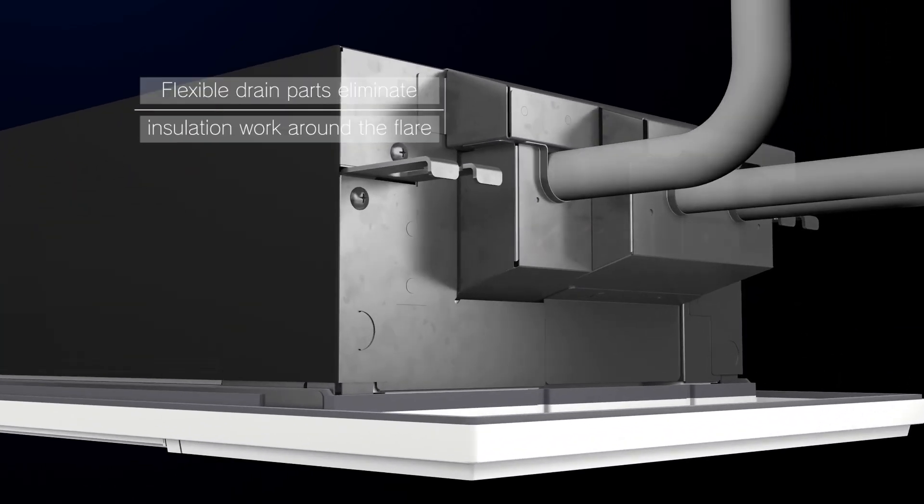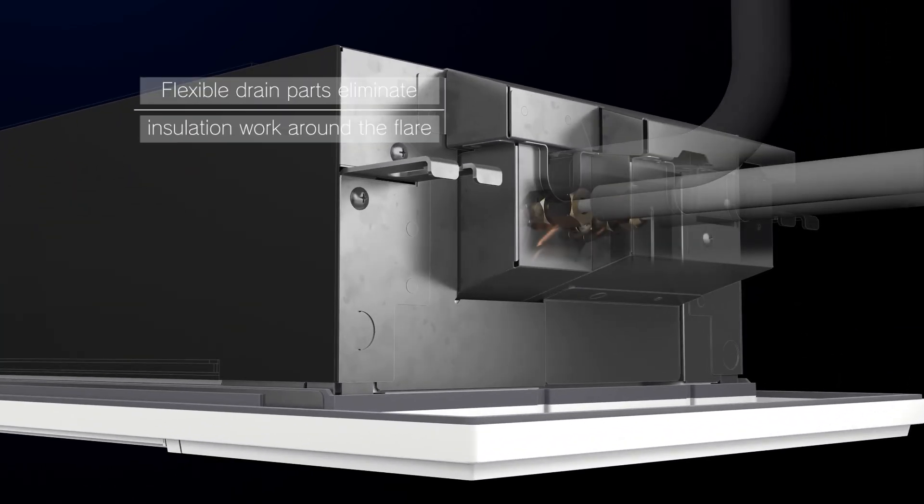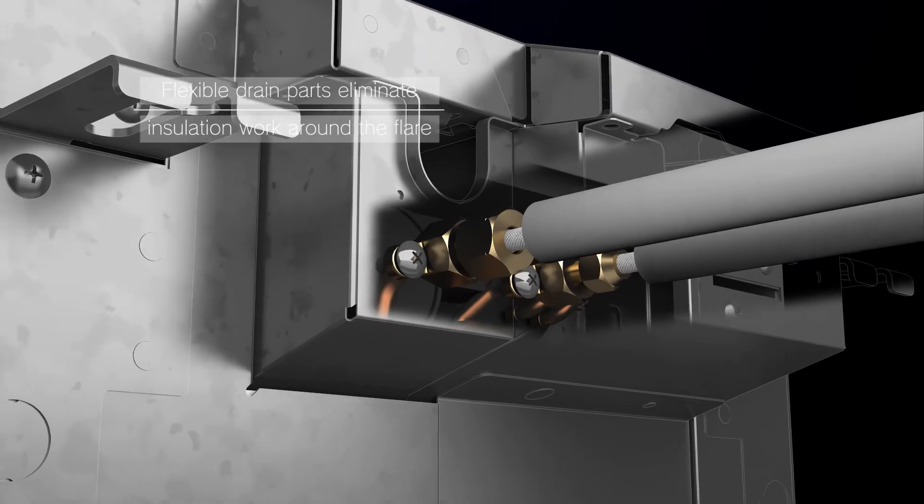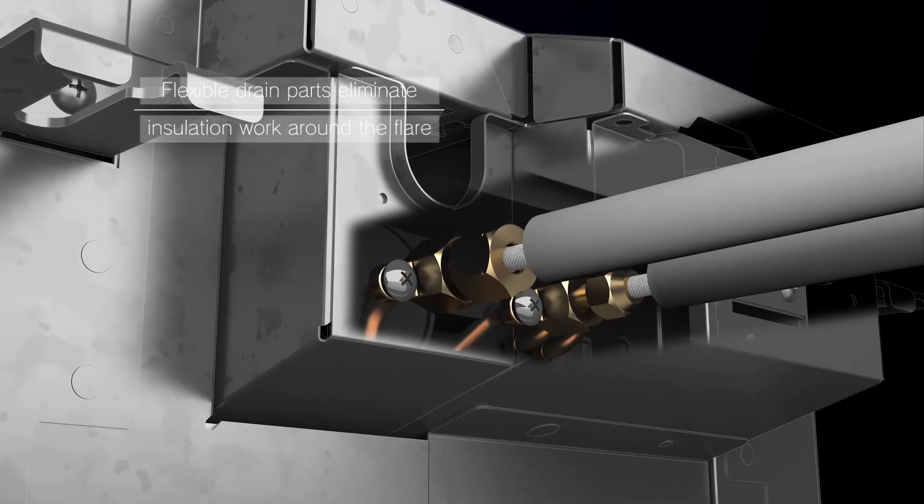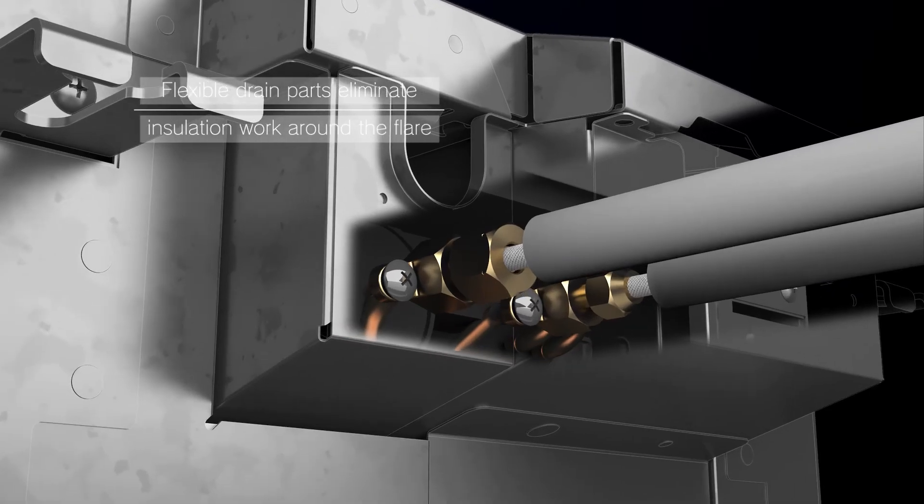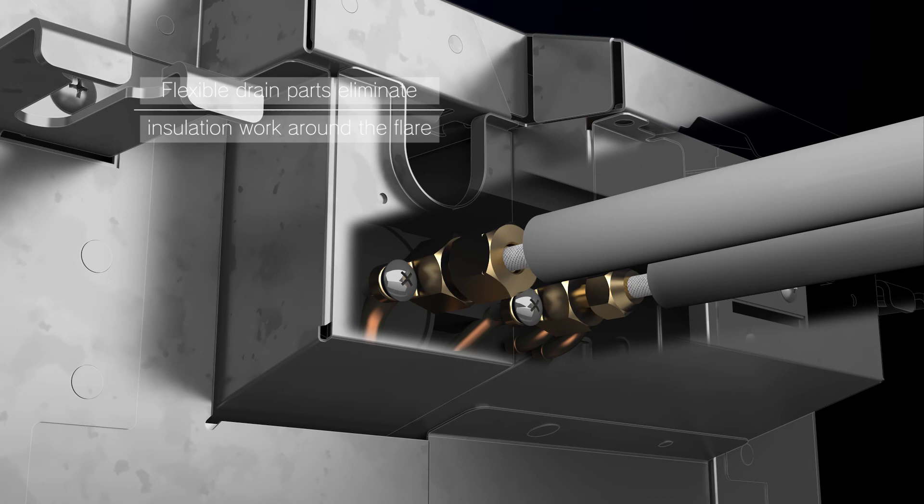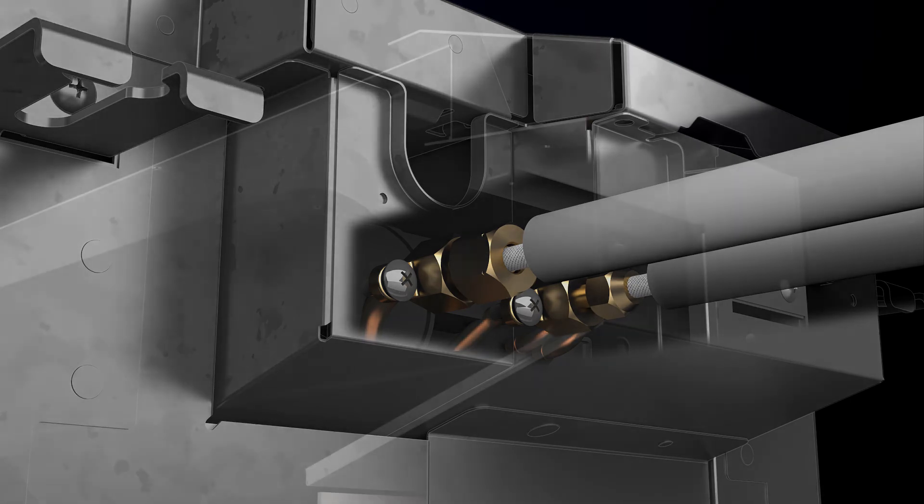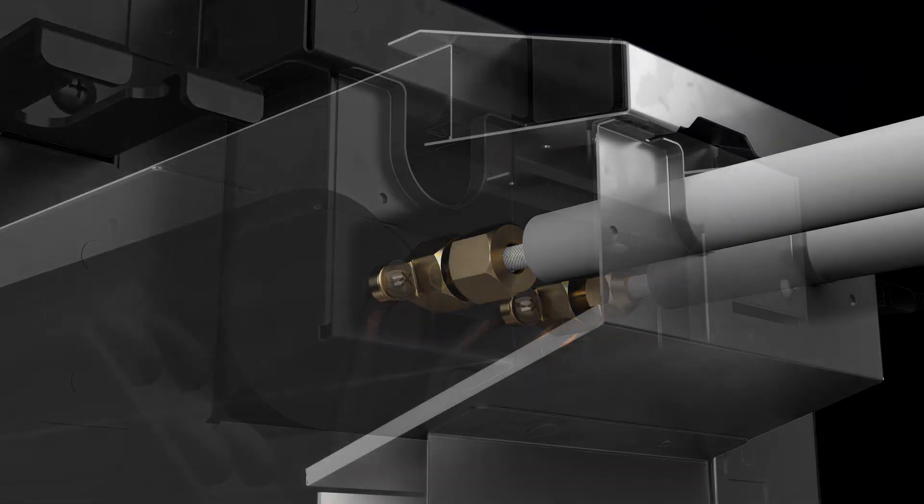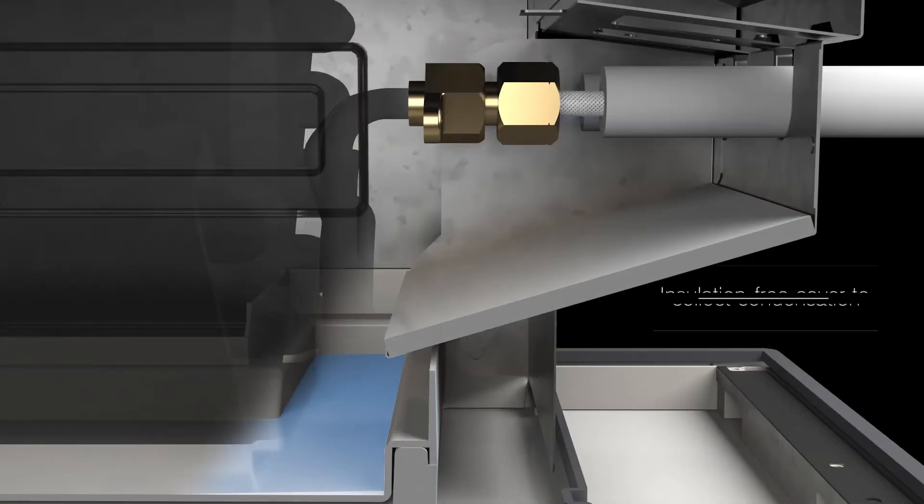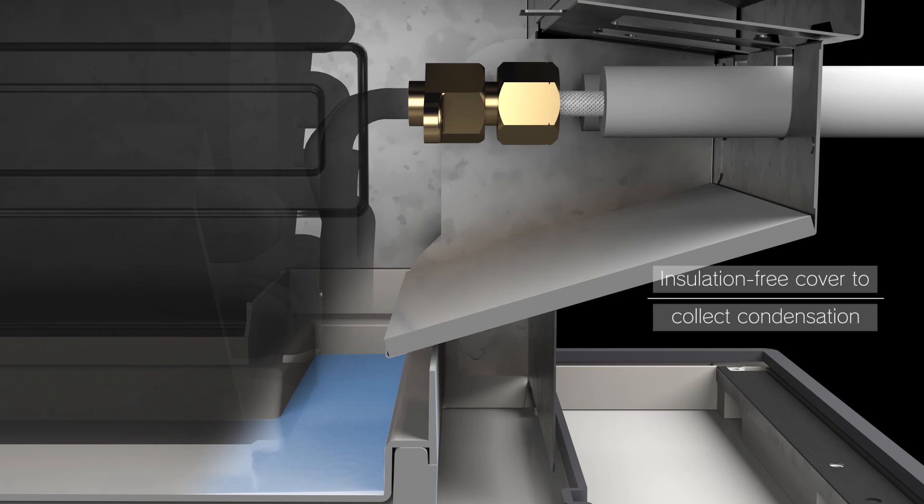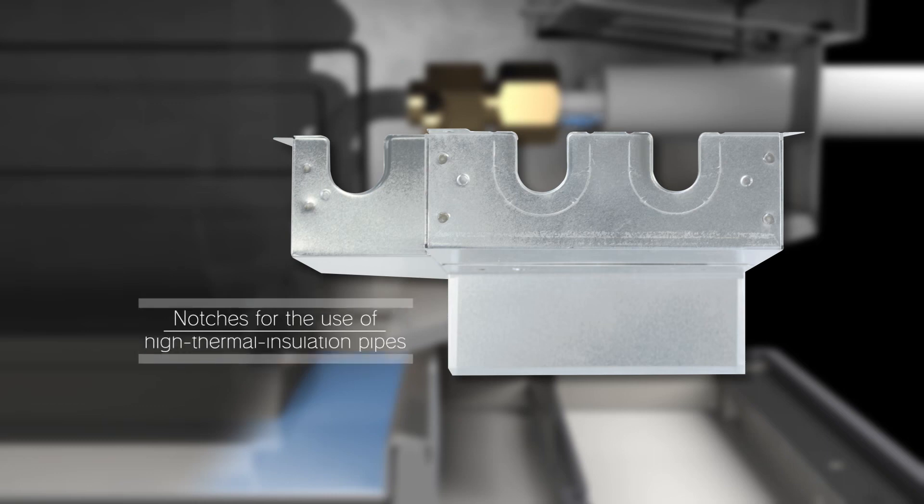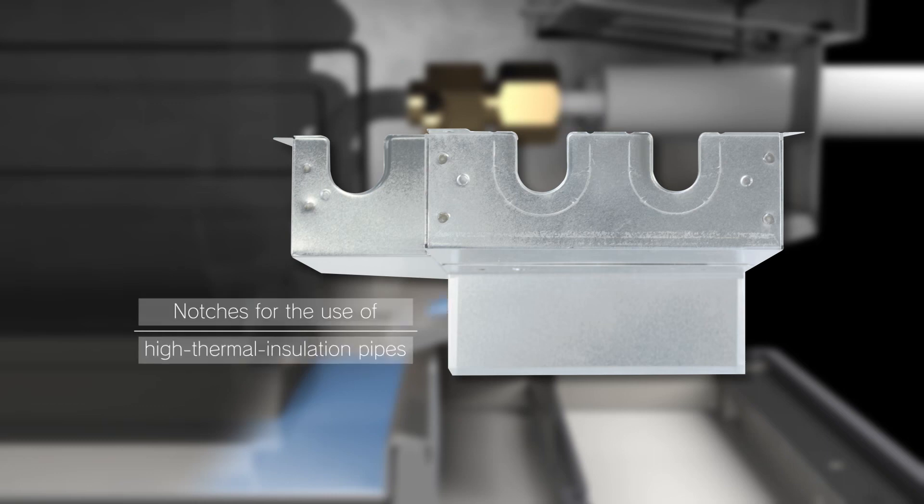The MLZ series utilizes flexible drain parts. Joint connection can be easily done with no required insulation work around the flare. The insulation free cover collects condensation in the drain pan. Notches are provided for the use of high thermal insulation pipes, resulting in improved workability.